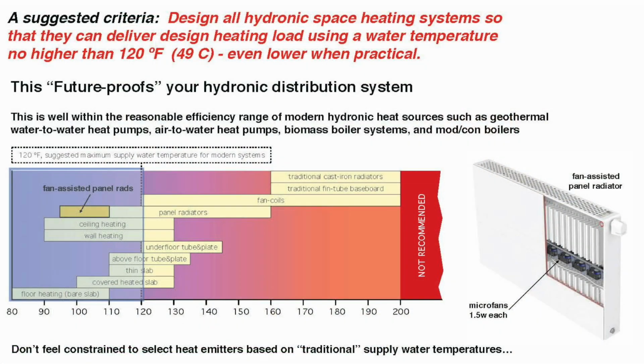And I suggest, and this is not a code or anything in the States, I suggest every hydronic system today, 120 degrees at design or lower. I go to 120, that's well within the operating envelope of heat pumps. ModCon boilers are going to work pretty well at that. That's at design. Obviously, with outdoor reset control, you can bring that water temperature down. And I'm not saying you always design for 120 if you can design a system around 100 degree water. We've actually got a project, I'll talk about it this afternoon, with panel radiators. And in February, we're heating it with 90 degree Fahrenheit water. So we can design systems for definitely lower than 120, but we should not go over 120.